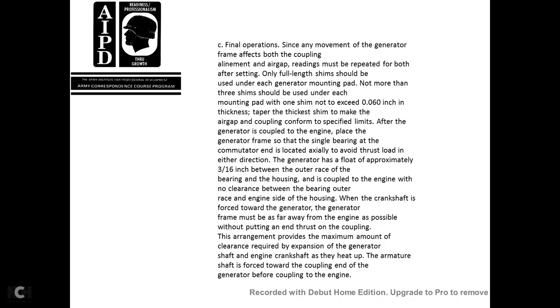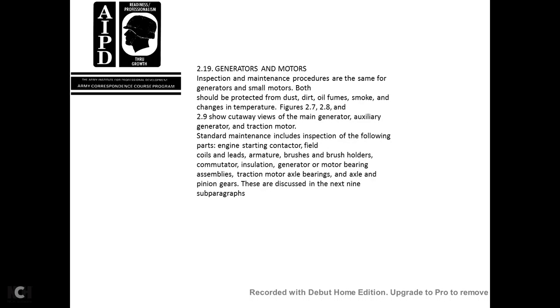Place the generator frame so that the single bearing at the commutator end is located axially to avoid a thrust load in either direction. The generator has a float of approximately 3/16 of an inch between the outer race of the bearing and the housing when coupled with the engine, and no clearance between the outer race of the bearing and the engine side of the housing. When the crankshaft is forced toward the generator, the generator must be able to move away from the engine, if possible, without putting an end thrust on the coupling. The arrangement provides for the maximum amount of clearance required by expansion of the generator shaft and engine crankshaft as they heat up. The armature shaft is forced toward the coupling end of the generator before coupling to the engine.